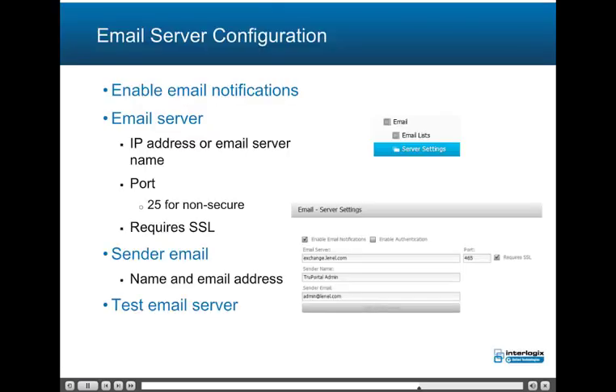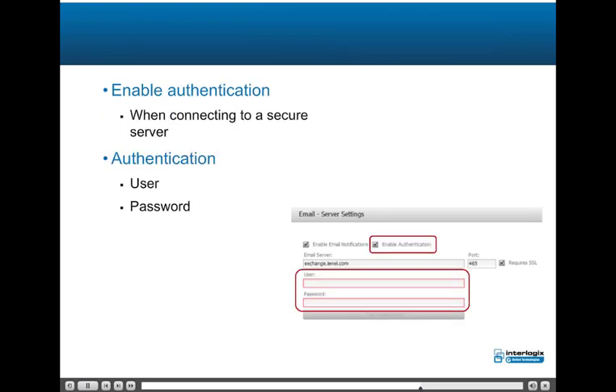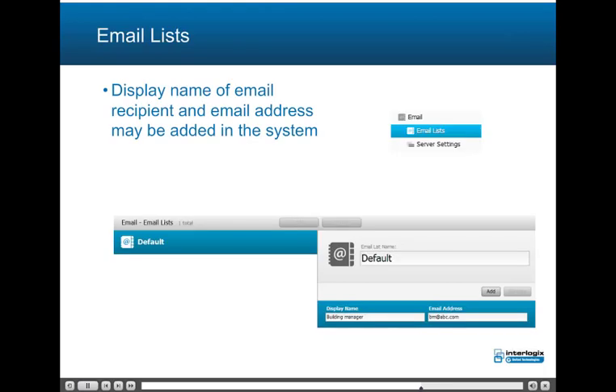Email server configuration: enable email notifications, configure email server IP address or email server name, port (25 for non-secure), SSL requirement, sender email name and address, and test email server. When connecting to a secure server, enable authentication with user and password. Display name of email recipient and email address may be added in the system email lists.